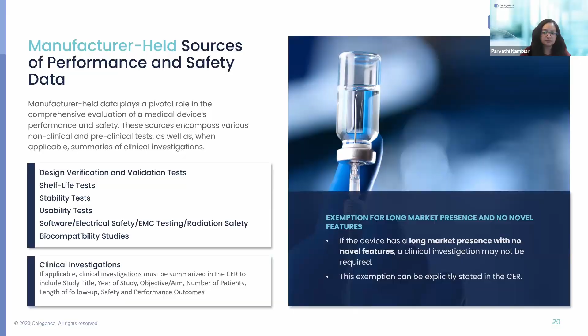Additionally, if there have been clinical investigations carried out on the subject devices, they also need to be presented in this clinical evaluation. An exception for this can be legacy devices and devices that do not have any novel features. For such devices, it is not necessary to have a clinical investigation in place, and the same can be stated in the CER also. It needs to be stated explicitly in the CER that for such and such reason, no clinical investigations were performed for the subject devices.